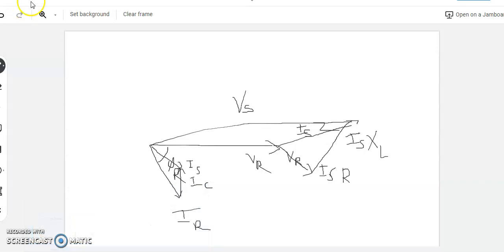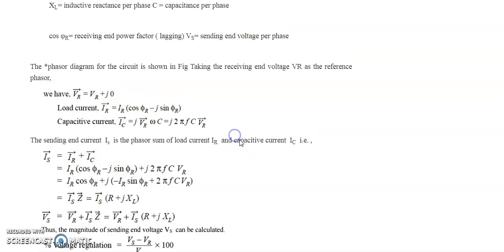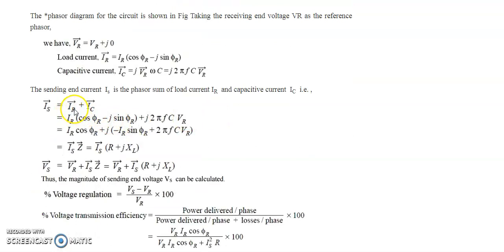Since we have considered the receiving end voltage as reference, the Vr vector equals Vr + j0, and load current Ir equals Ir·cos(φr) − j·sin(φr). The capacitive current Ic equals j·Vr·ωC, where ω can be written as 2πfC, multiplied by Vr. The sending end current Is equals Ir plus Ic. Elaborating these: the real part is Ir·cos(φr) and the imaginary part is −Ir·sin(φr) + 2πfC·Vr.